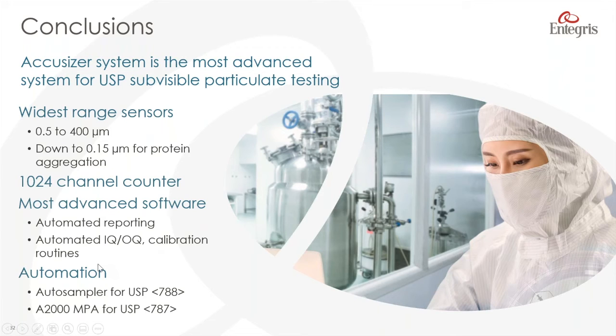We showed, as we talked about the automatic reporting and the calibration routines, the software we use to run the systems are the most advanced, making these measurements much easier and quicker for people performing these tests. And for people who need high throughput in the laboratories, we have two solutions for automation. We have an auto sampler for performing typical USP 788 tests, and the A2000 microplate analyzer for doing low volume tests when working with proteins following the requirements of USP 787.